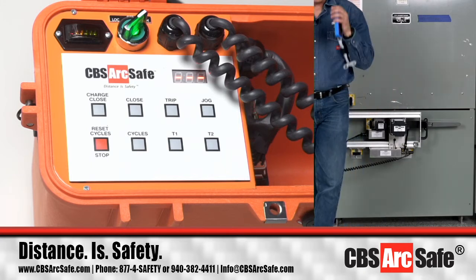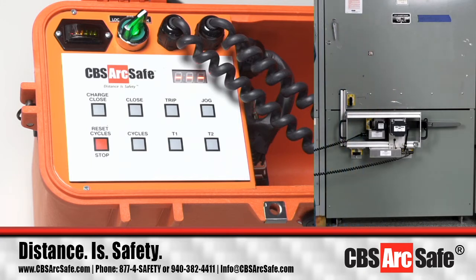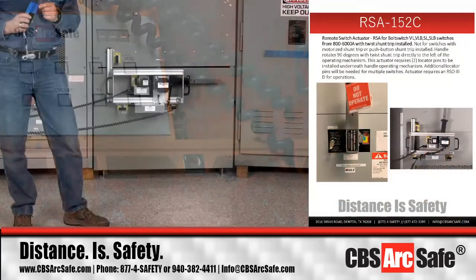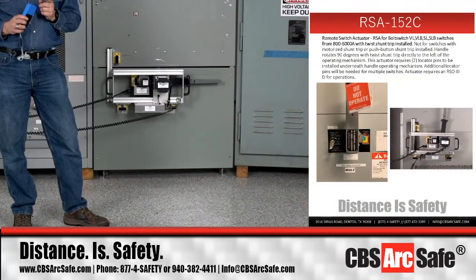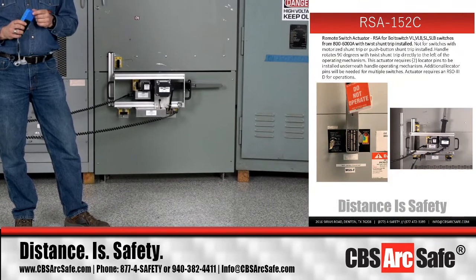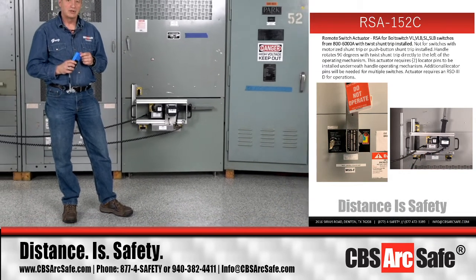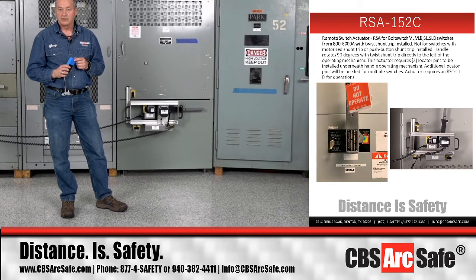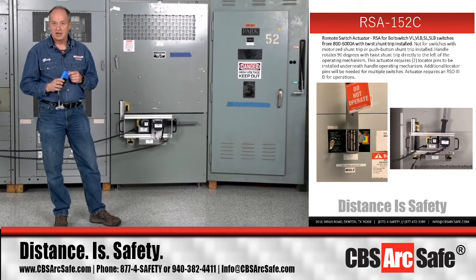Some of the guidance we were given a long time ago when we started is never let a customer close a breaker without being able to open it right away. That's the reason we want to have both the close and the trip on it when you're going to operate the switchgear.